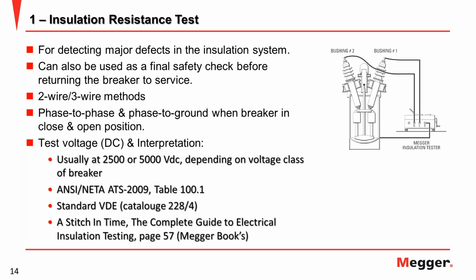As you know, the insulation system for metal enclosed switchgear is designed based upon a life expectancy of maybe more than 30 years. However, environmental conditions such as dirt, moisture, and corrosive atmosphere can reduce the lifetime of the insulation. Especially moisture combined with dirt is the greatest deterioration factor for the insulation system because of leaking and cracking, which will result in eventual failure. So this is very important to test first, before you do other testing. You need to test the insulation resistance to make sure there is no high leakage current between insulators.